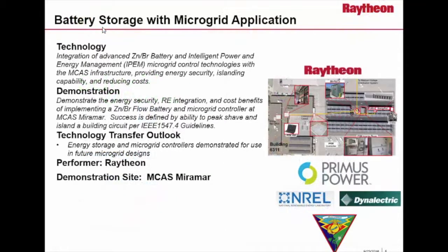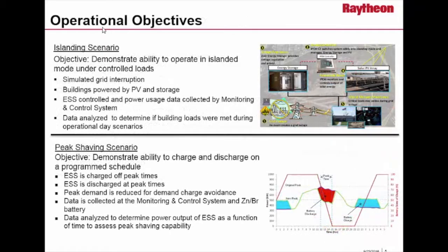I got involved with this project back in about 2012. The scope here was to install energy storage to cover a couple of use cases at Building 6311 at MCAS Miramar. The battery chosen was a zinc bromide flow battery, spec'd at 1 megawatt hour, and we were also using existing PV, about 230 kilowatts of carport PV installed on the base, integrating that existing hardware with a microgrid controller we developed to perform both islanding—the ability to isolate from the utility and work off-grid using 100% renewables—and peak shaving to offset the peaks of the building.